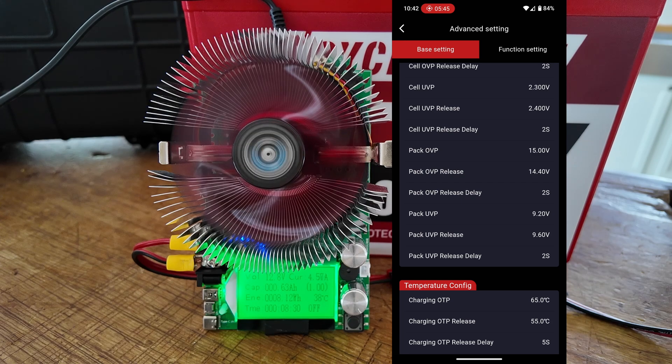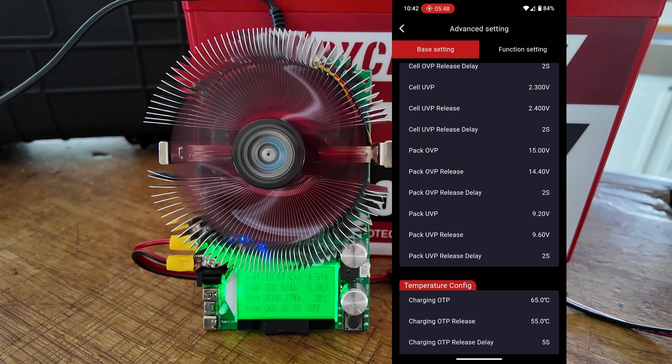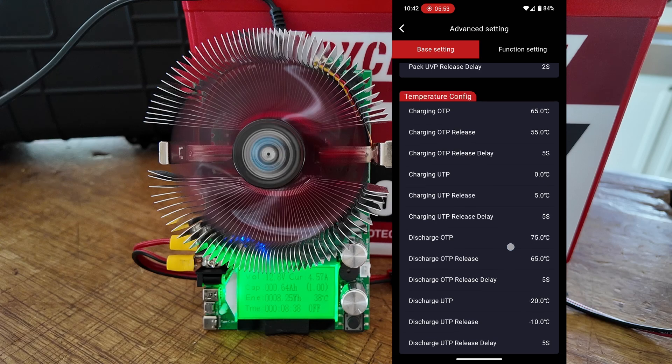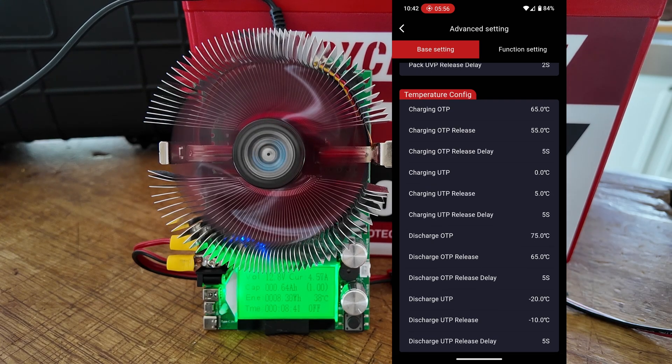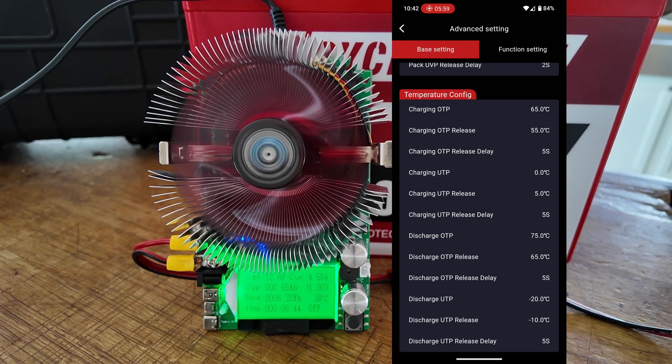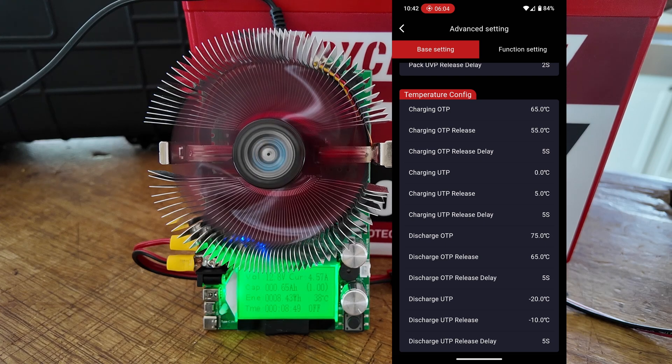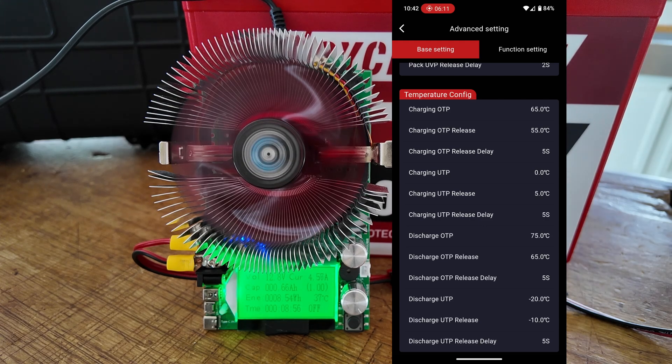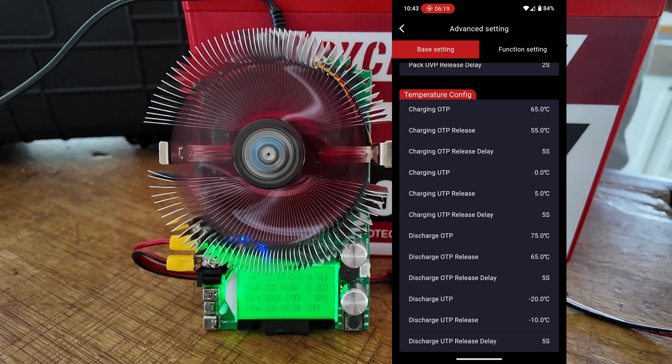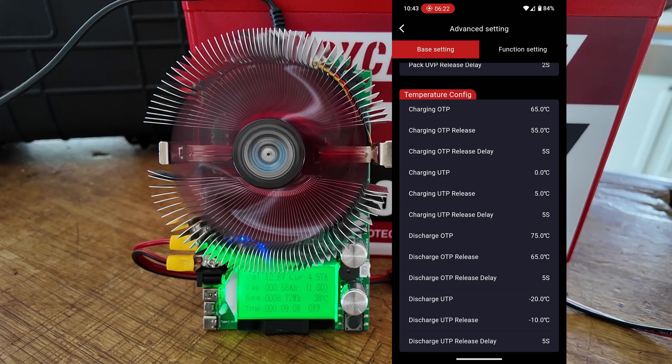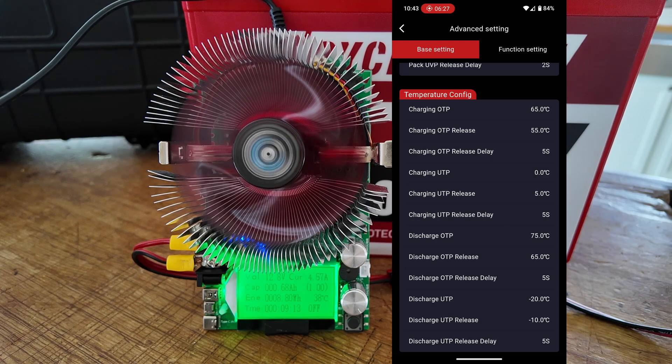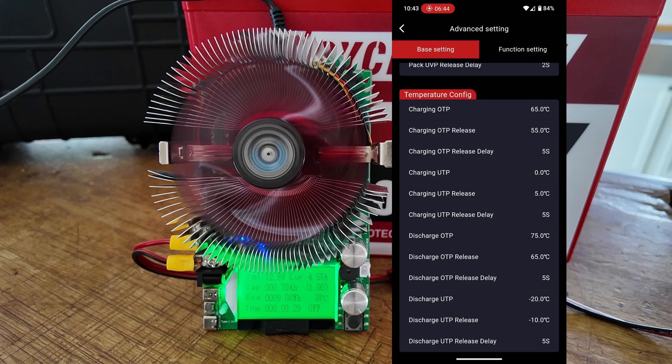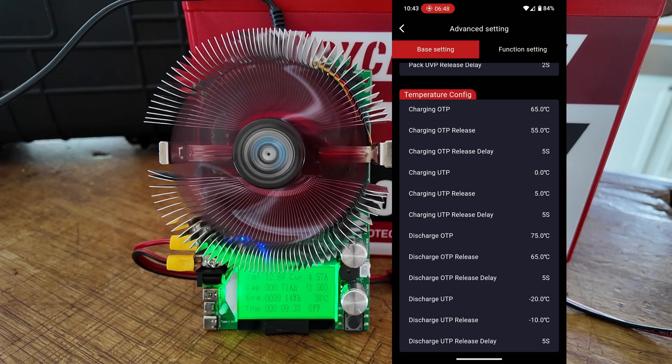And then the under-voltage protection for the entire pack right now is set to 9.2 volts, and the release is at 9.6 volts. Below that, you also have the option to change the temperature configuration, and this is one of the coolest things for this particular pack. You can see the over-temp protection for charging is set at 65 degrees Celsius, and I have no reason to believe that I will ever be trying to charge this battery if it's hotter than that. The one that I'm a little bit more interested in is the under-temperature protection, and you can see right now that that is set to 0 degrees Celsius, and it will not charge until it gets back up above 5 degrees Celsius. That's going to protect this battery to where it cannot be charged while it's freezing.